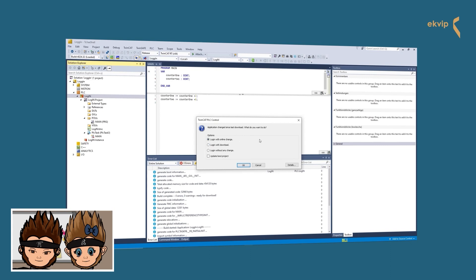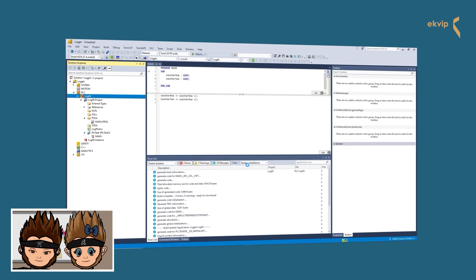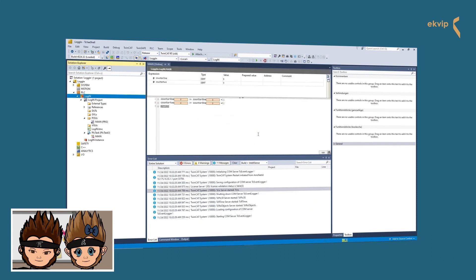During an online change, a running program is not stopped — only the modified parts are reloaded into the controller. You could use this option if you did some minor modification of the project. If you did a lot of modifications, this can cause trouble because the program behavior cannot be predicted reliably. In that case, we recommend selecting Login with Download. If we download the changes, the program will be stopped and a new compilation is triggered. This option is recommended by Beckhoff since it always leads to a defined output state as a result of the program stop and reinitialization.